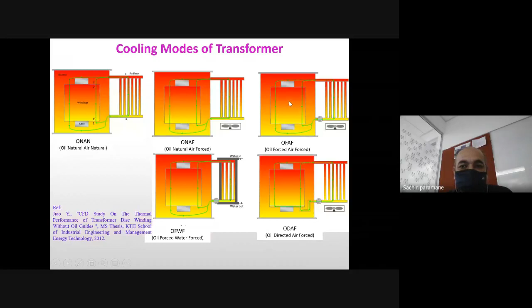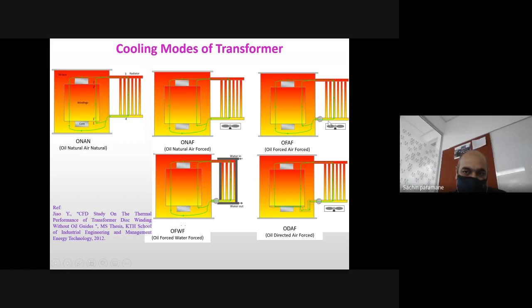Then, as load on the transformer increases, oil is also forced inside the tank and heat exchanger. For forcing the oil, a pump is used. So this pump forces the oil in the transformer. So it is called oil forced and air forced. Oil is forced as well as air is forced.